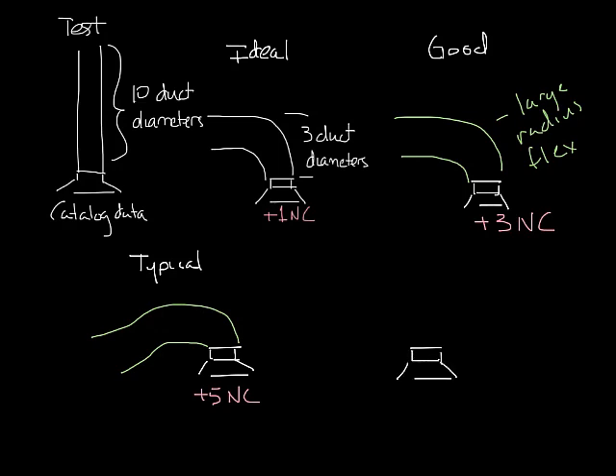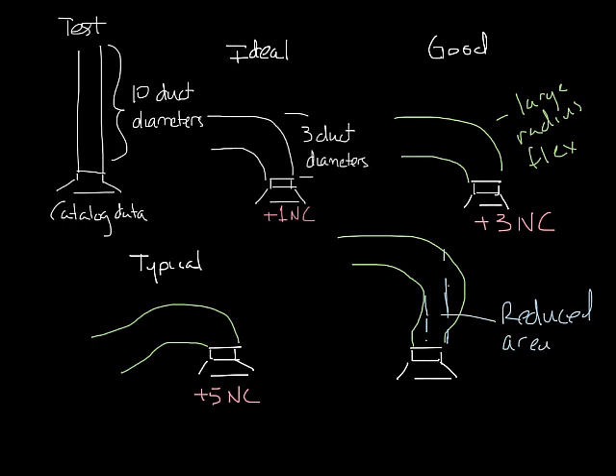The worst case is when there's too much flex duct used. It may kink or obstruct the inlet of the diffuser, which reduces the free area, increases the pressure drop, and increases the sound. An installation like this could add 7 to 9 NC over what the catalog data says. You can see that installation has a large effect on sound of VAV boxes and diffusers.